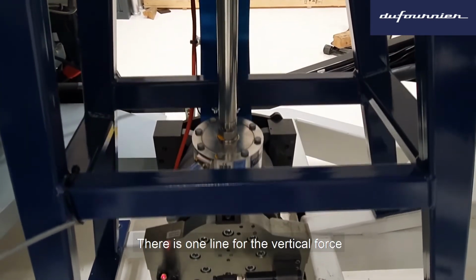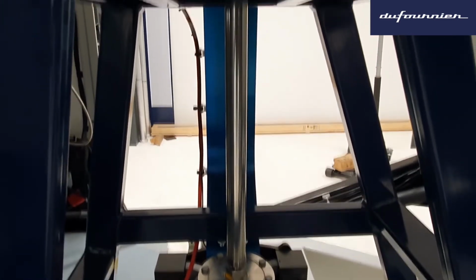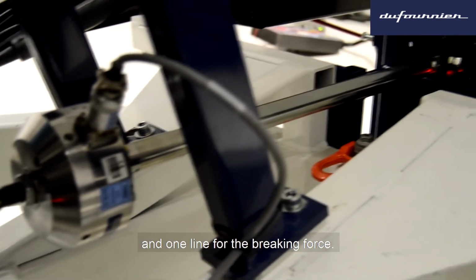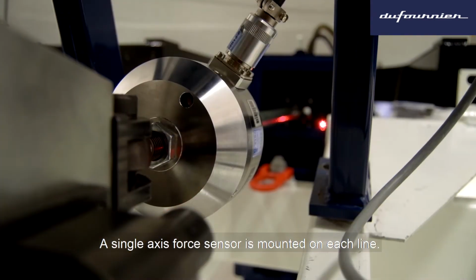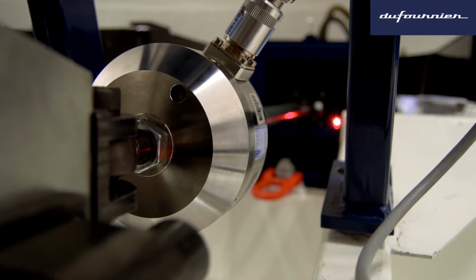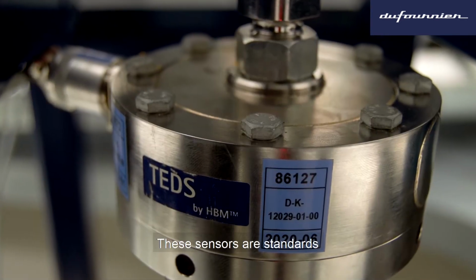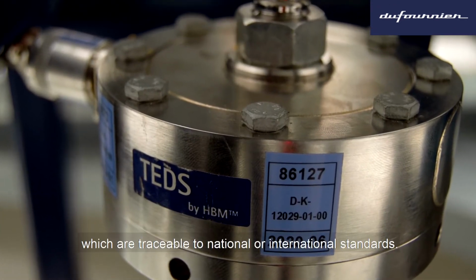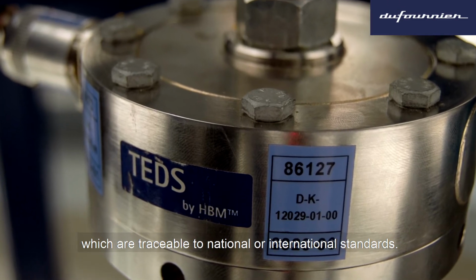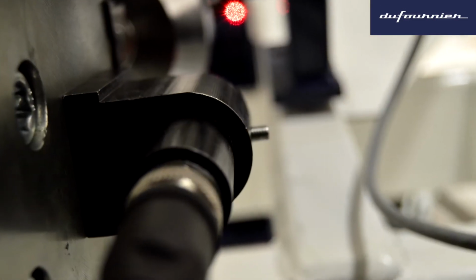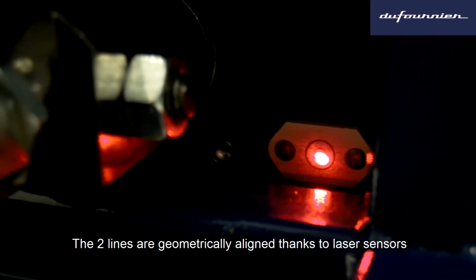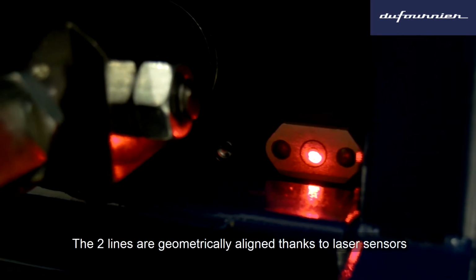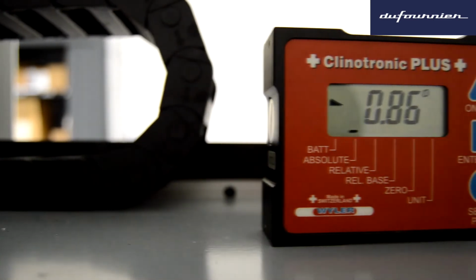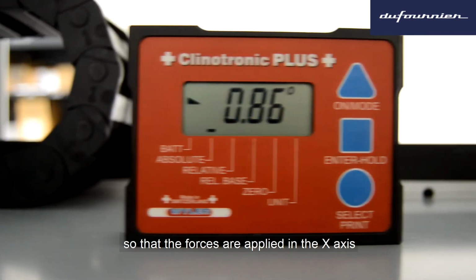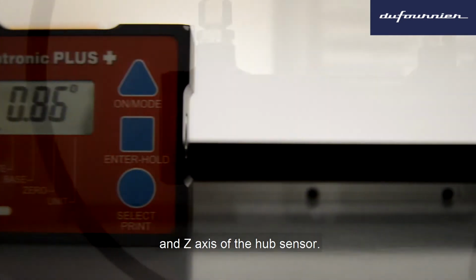There is one line for the vertical force and one line for the braking force. A single axis force sensor is mounted on each line. These sensors are standards which are traceable to national or international standards. The 2 lines are geometrically aligned thanks to laser sensors and an inclinometer, so that the forces are applied in the x-axis and z-axis of the hub sensor.